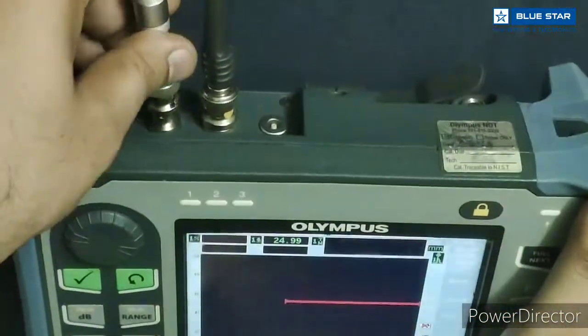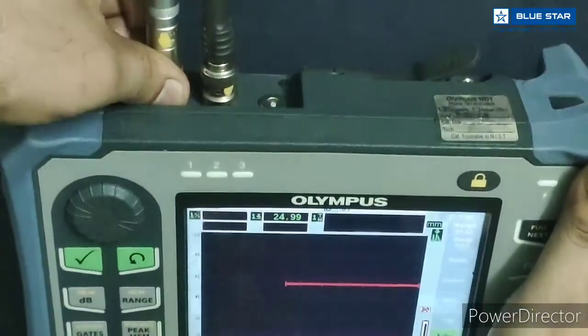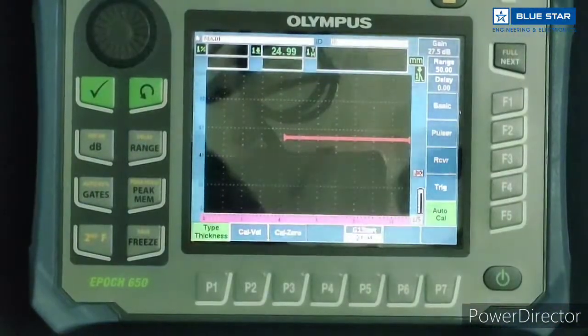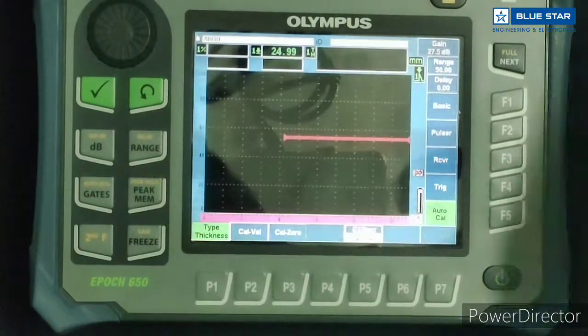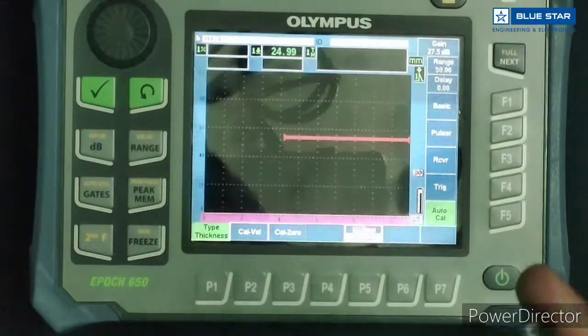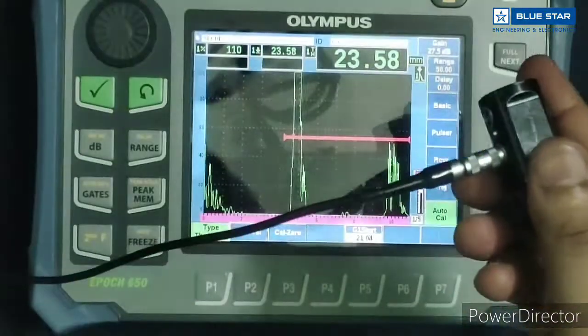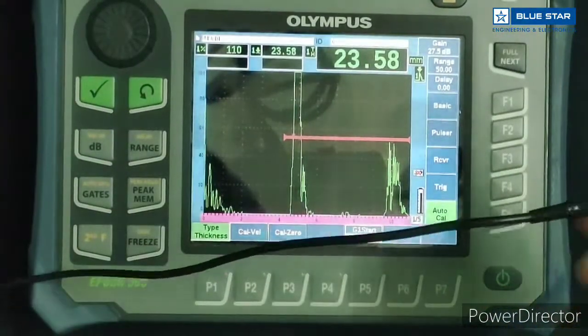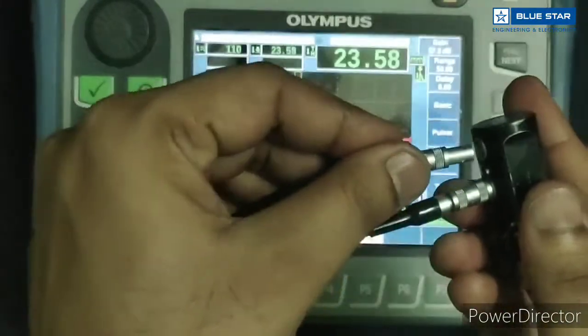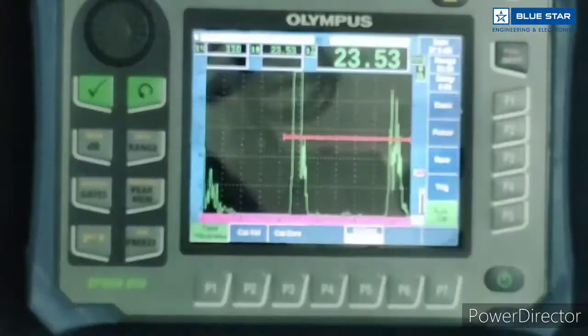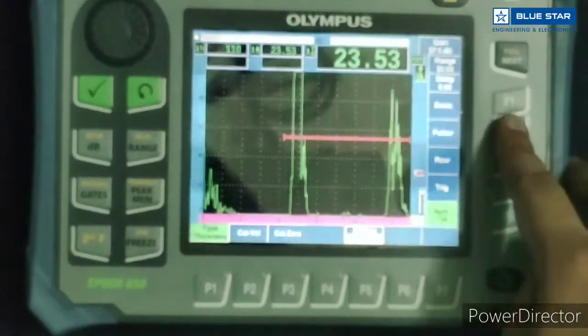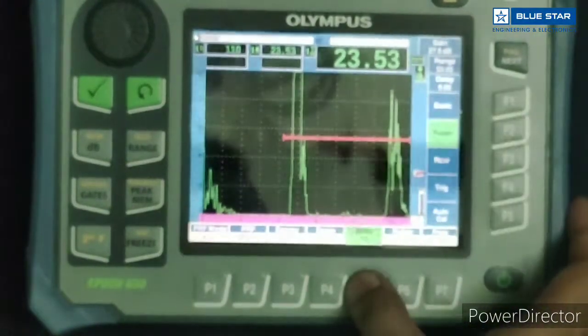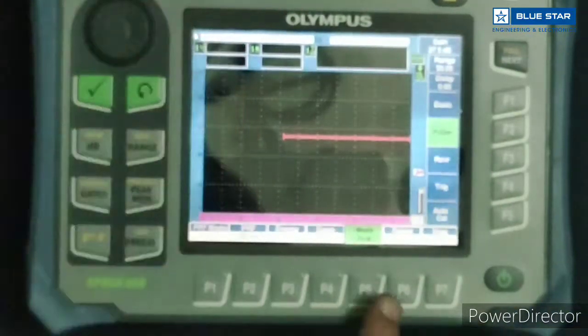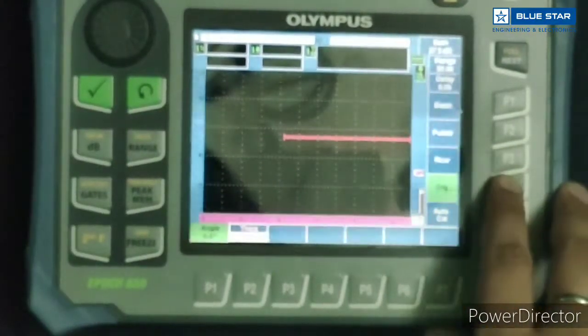Calibration of dual crystal transducer. Connect two cables, connect probe. Go to basic, select range 50 mm, go to pulser mode dual, go to trigonometry, angle should be 0 and go to AutoCal.